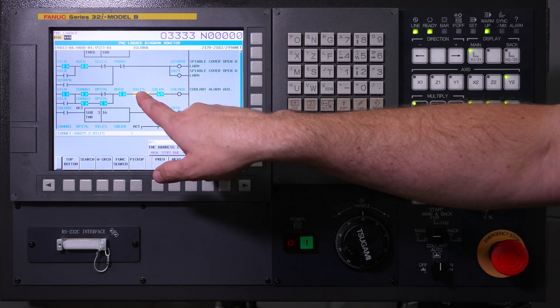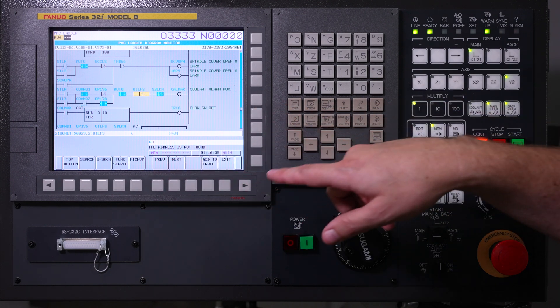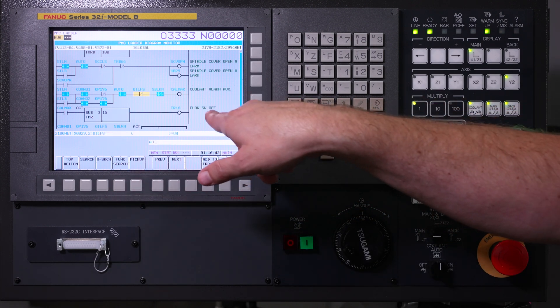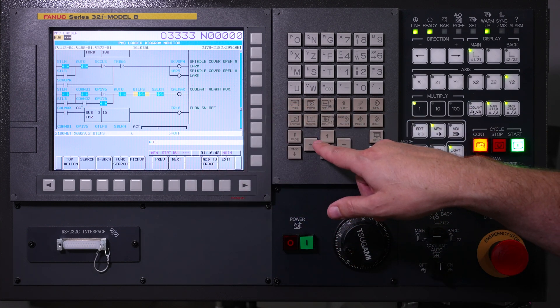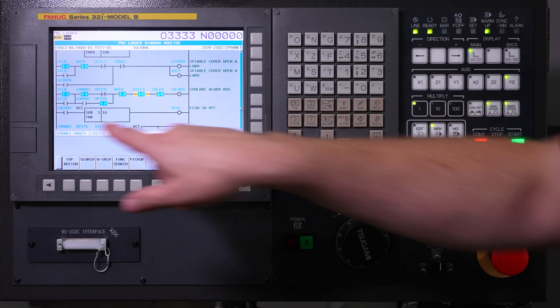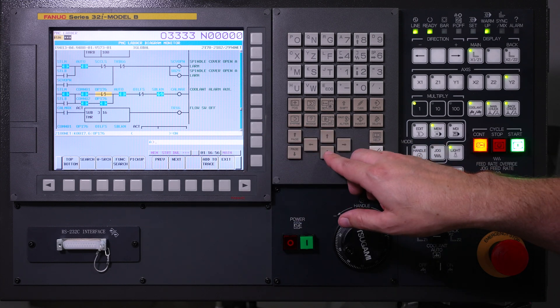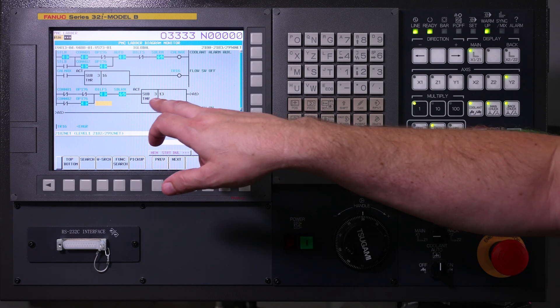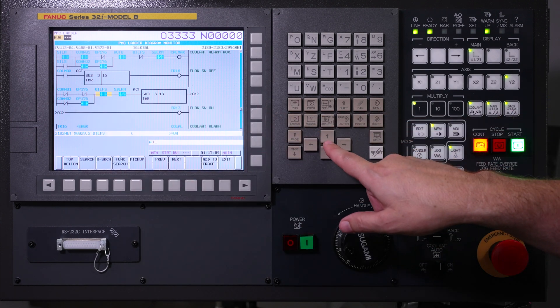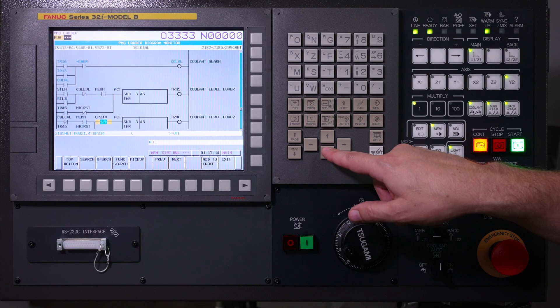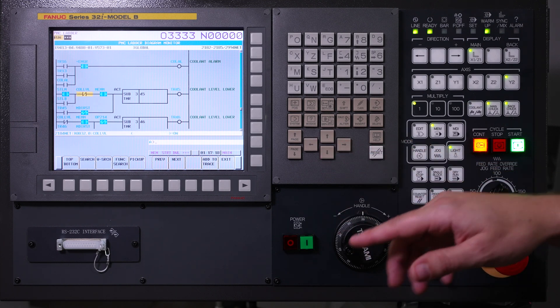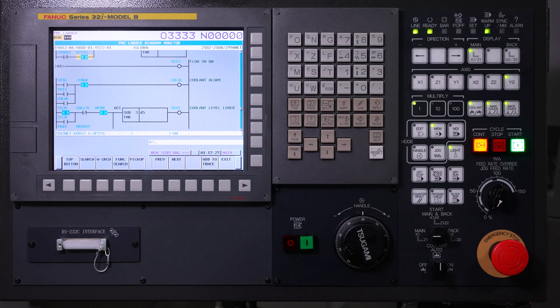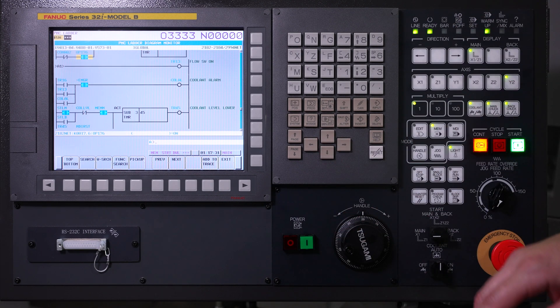Your input is showing there, and as it's running you'll see it flipping through. These are your timers. Timer 16 is your flow switch off. If you toggle out you'll see your inputs. OPs are your keep relays. If you scroll down you'll see your flow switch on, which is Timer 13, and you'll see that flipping. Here is your level — you'll have your level lower. Your coolant level is perfectly fine. You have separate timers for your coolant level switch, and as you can see these are tied onto the same alarm.